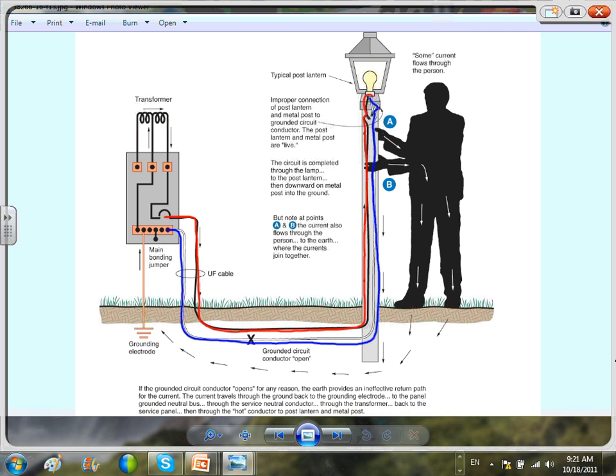Now, some people can say, well, this pole is in the ground, it's grounded through the pole. No. What the code requires you to do is take a second conductor here, a grounding conductor, directly, and tie it to the fixture. Does the UF not carry a ground? Yes, it does carry a ground, typically now. But long story short, they don't want you to depend on the ground. The ground shall not be a means of return for the ground fault. It's high impedance.